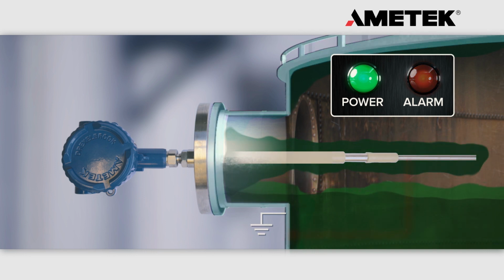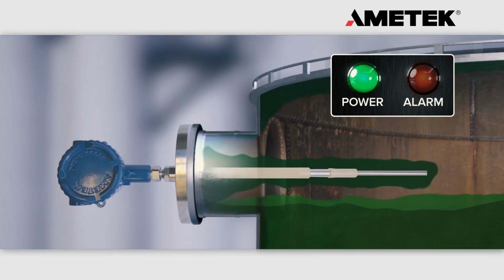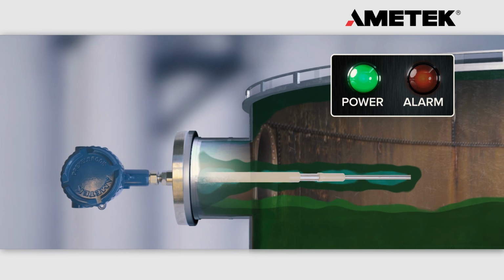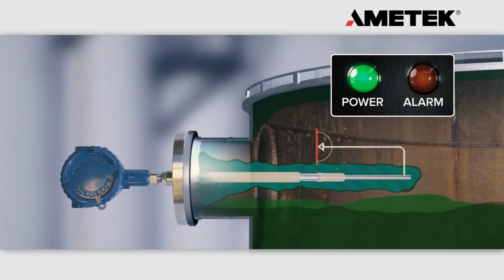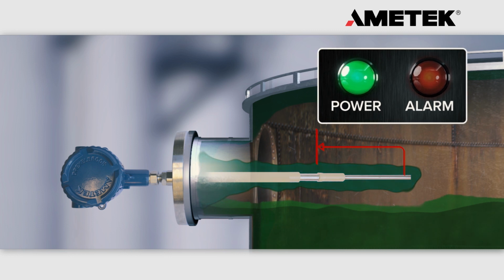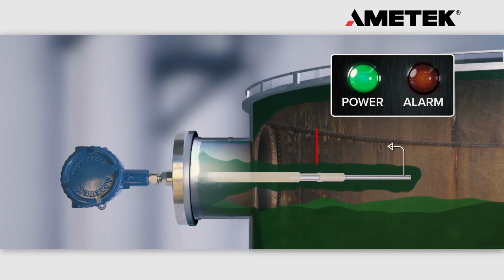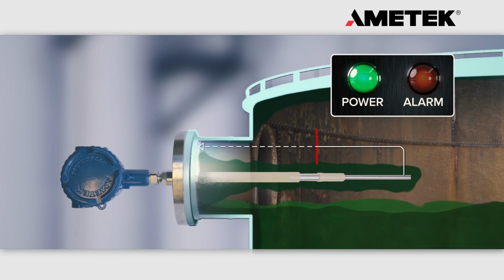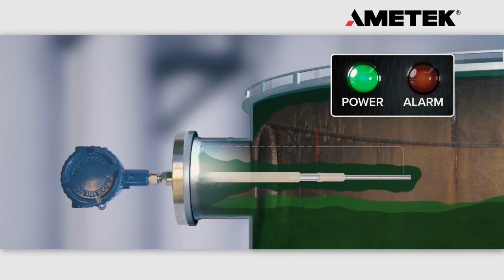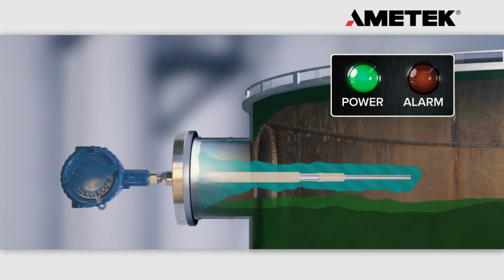No alarm. The reason for this is that the Cote-Shield element is blocking the only remaining path to ground. Remember, for an alarm to occur, an electrical circuit needs to be completed from active rod to ground. Without the liquid covering the probe, the only path available is from the active rod through the coating to ground. But with Cote-Shield, that path is blocked.